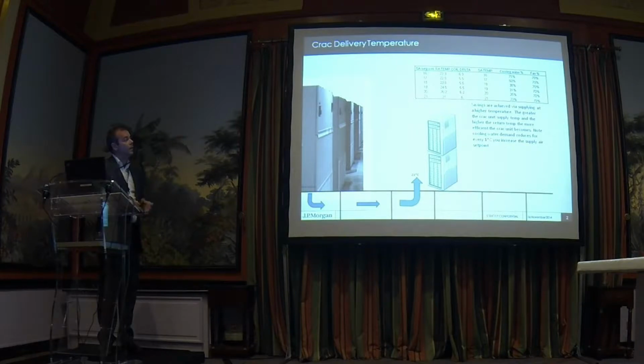So it pays to run at a higher temperature. At the end of the day, the server isn't going to thank you for running at a cooler temperature. You can run it as hot as you want, but it all depends on where your UPS power starts to ramp up and you start seeing higher server inlet temperatures. But the interesting thing is that it's still at the same delta across the machine.